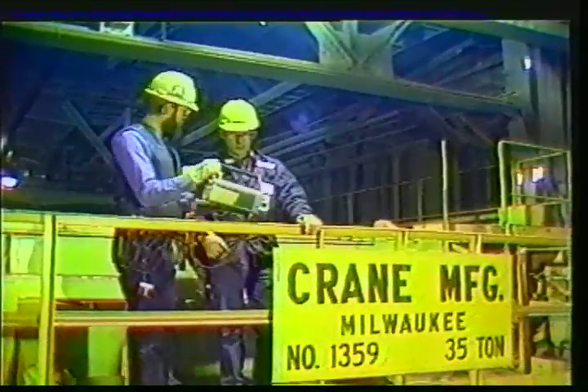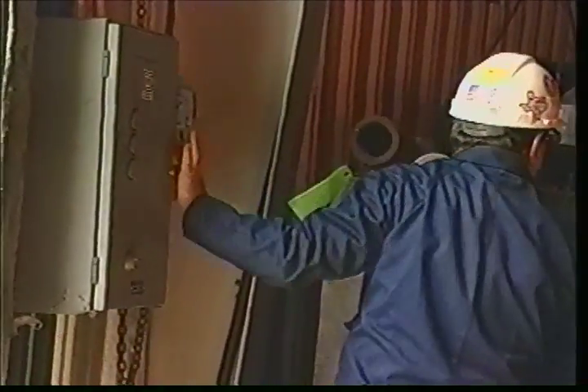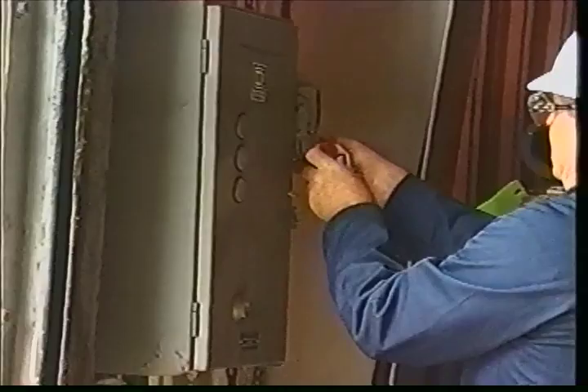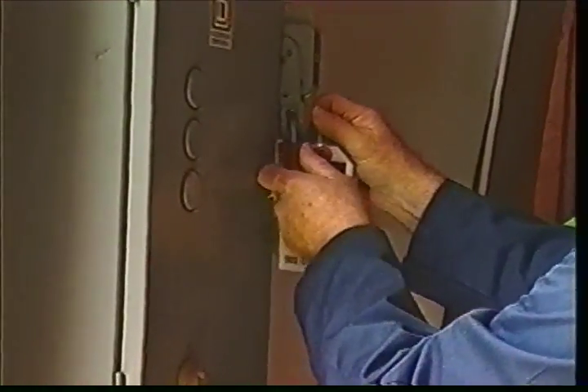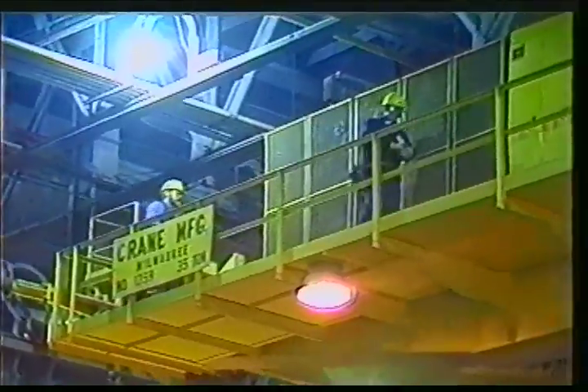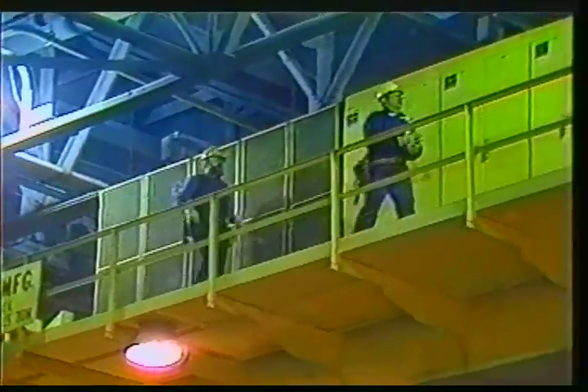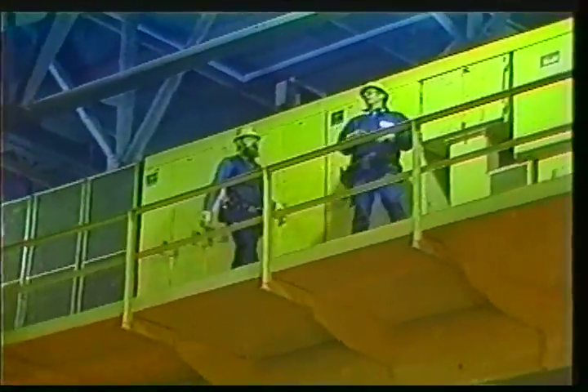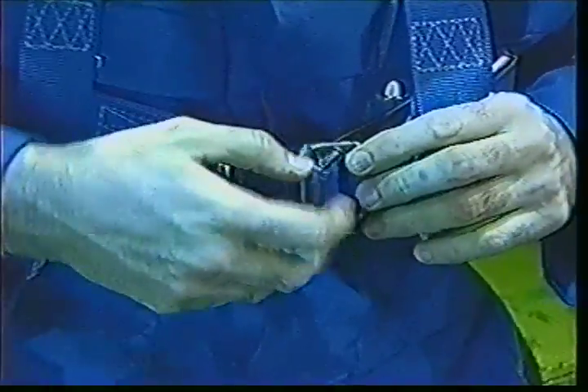When working near crane rail collectors, lock out the collector system if possible, or insulate the collector rail. Always get approval before starting work. When using the crane as a work platform, lock out the crane if possible. If it is necessary to move the crane during work, keep the pendant or transmitter on the bridge with the work crew. Make sure other cranes in the same bay are isolated from the crane being worked on. Also, you must use proper fall protection if you are working beyond the limits of guardrails and other fall prevention devices.